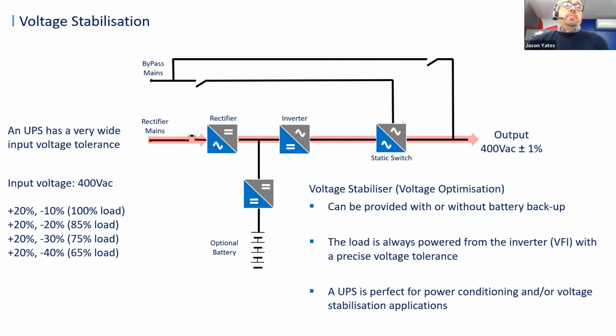And therefore, the benefit of this is that an online UPS system can operate as a true voltage stabilizer, and also, if required, can be provided with or without battery backup. It doesn't need to have batteries connected to do this. Obviously, the load is always powered from the inverter, VFI, which stands for voltage and frequency independent. Basically, it means whatever comes into the UPS is not passed to the connected load, and that operates with a very precise tolerance. Basically, a UPS system is a perfect power conditioner and/or voltage stabilization application.